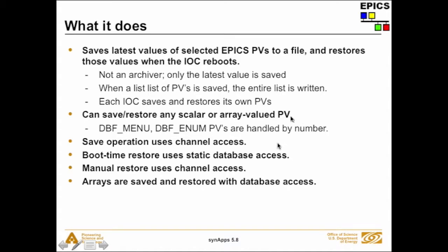It can save and restore any scalar or array valued PV, but for some PVs, DBF menu PVs and enum PVs, it doesn't save the string, it just saves the number. So you have to be careful if those strings change in between reboots.